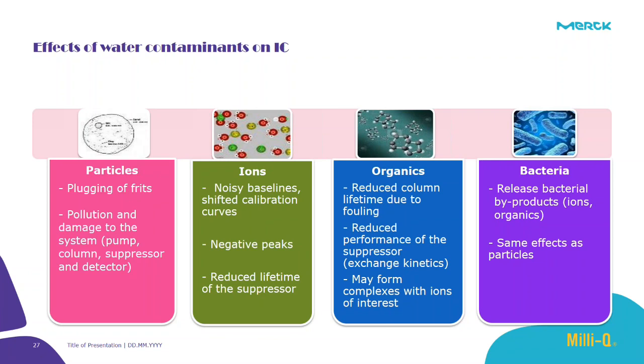Second, the contaminant is the ions, which may cause noisy baselines, shifted calibration curves, negative peaks, or reduced lifetime for the suppressor. Third, the contaminant is the organics, which may reduce the column lifetime, reduce the performance of the suppressor, and may form complexes with the ion of interest.